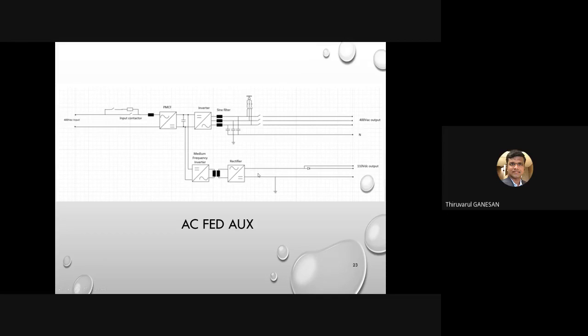This is an AC fed auxiliary system, for example the front end converter fed by AC, like 25 kilovolt or 15 kilovolt, which will be converted into DC. This is a DC bus and inverter portion, and it will be converted into control for the auxiliary loads. This is a circuit for medium voltage medium frequency converter, where the DC is converted and stepped down into 110 volt, which is used to charge your battery.